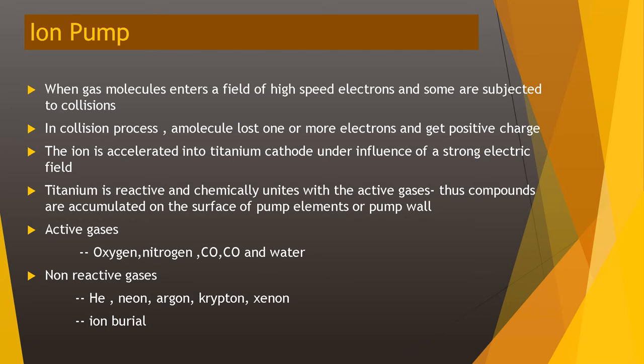When gas molecules enter a field of high-speed electrons, some are subjected to collisions. In this collision process, a molecule loses one or more electrons and gets a positive charge. The ion is accelerated into the titanium cathode under the influence of a strong electric field. Titanium is reactive and chemically unites with active gases, and the resulting compounds accumulate on the surface of pump elements or on the pump wall.